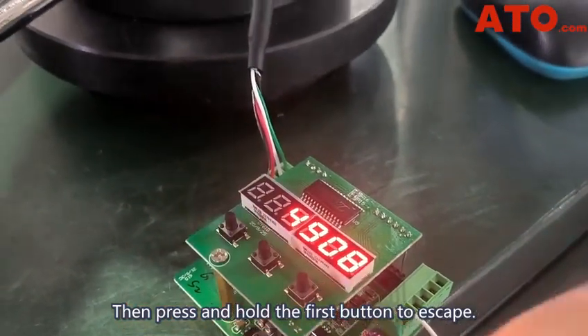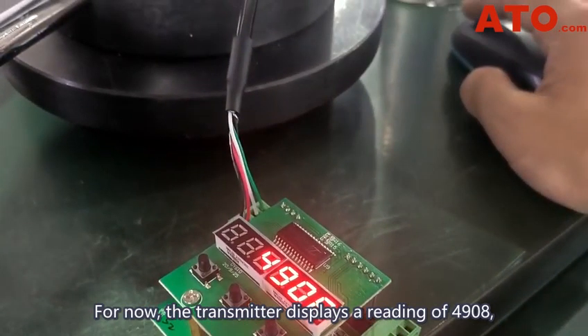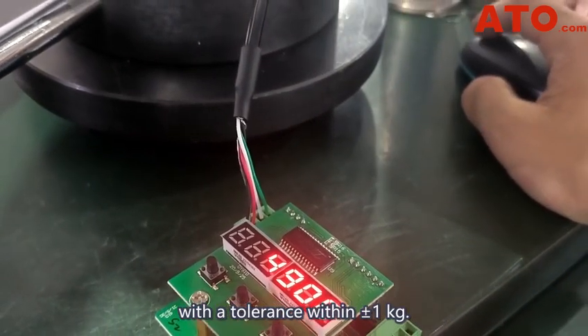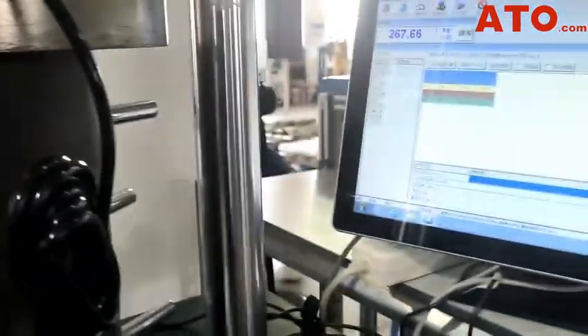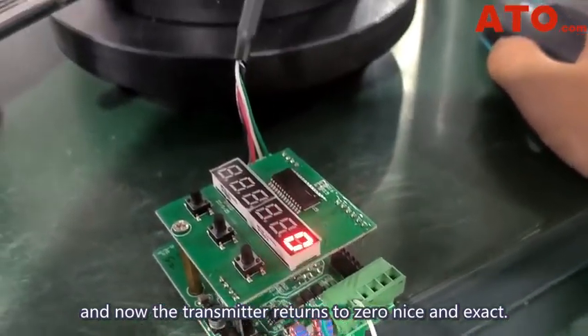Then press and hold the first button to escape. The transmitter now displays a reading of 4908, with a tolerance within ±1 kg. Remove the applied force, and now the transmitter returns to zero — nice and exact.